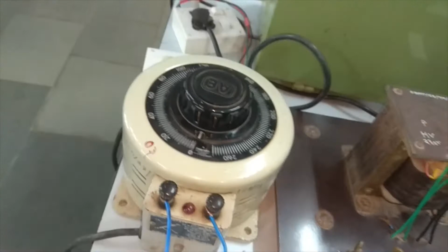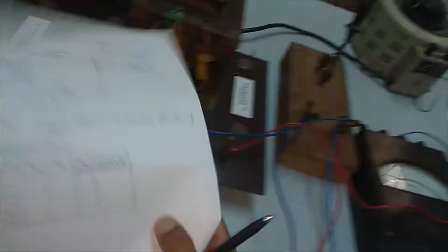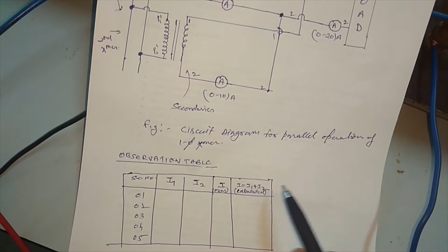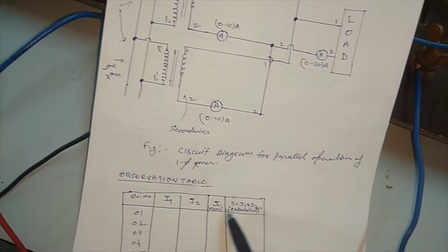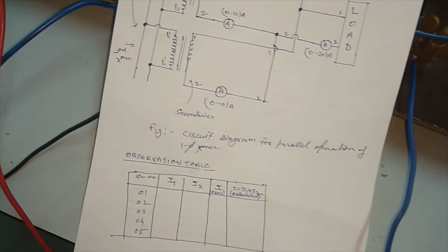The other thing we can do is set up the ammeters like this. This ammeter gives the current for the first transformer, this one gives the reading for the second transformer, and this gives the total reading. We will write these in our observation table: I1, I2, and I, the third ammeter. We can calculate I1 plus I2, and it should equal I, so we can determine if there is any error in the reading.